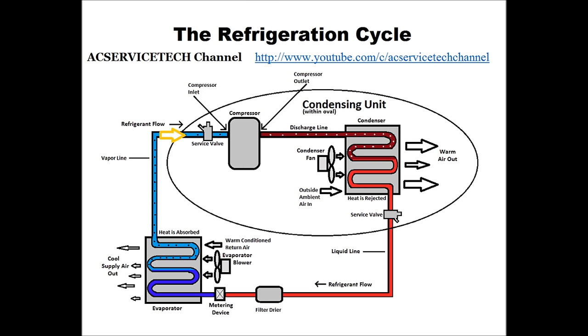What you have is a low pressure, low temperature vapor coming into the compressor, and then high pressure, high temperature vapor coming out at its hottest point. It then enters into the condenser coil where it starts to reject heat until it becomes a saturated state where vapor and liquid both exist. After that, it rejects more heat as a liquid, exits its saturated state, turns into a liquid, and continues to drop in temperature until it comes out past the valve.